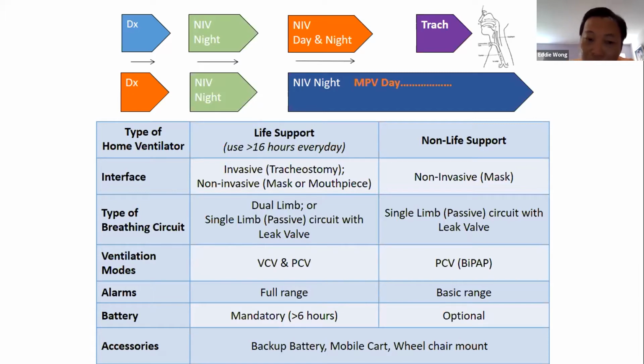Okay. So ventilation mode, basically for life support ventilator, there are two different modes you can choose from: volume control or pressure control. For non-life support, there is only one type of mode of ventilation, which is pressure control ventilation, or in another term we call bi-level positive airway pressure.